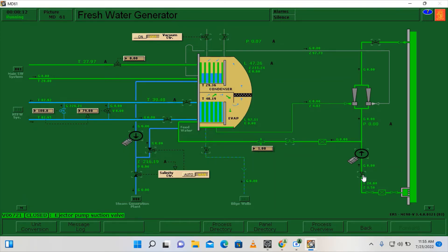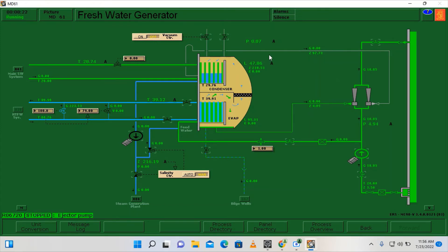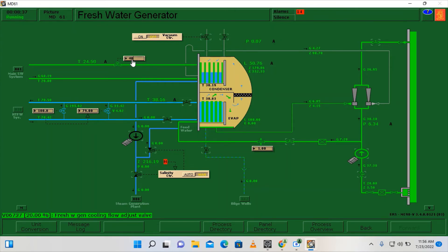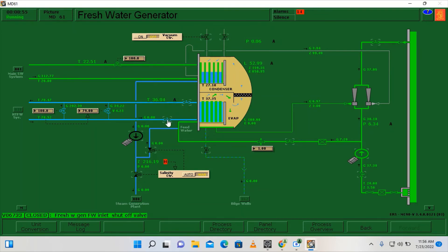Close afterwards and then we need to put our fresh water generator back on service, following the same procedures as before. Gradually open the valves, then gradually open again, and release the alarm by pressing Shift+F2 to silence it. Open the outlet and inlet valves of our HT and slowly adjust, then close the bypass valve.